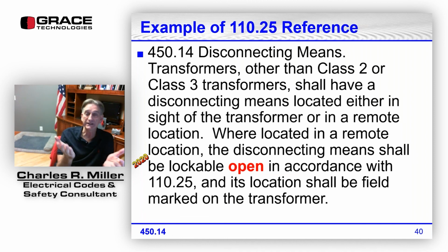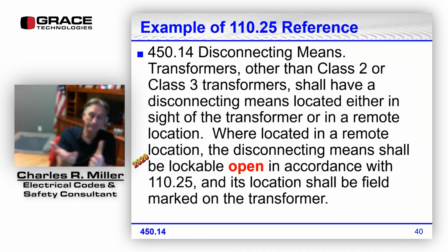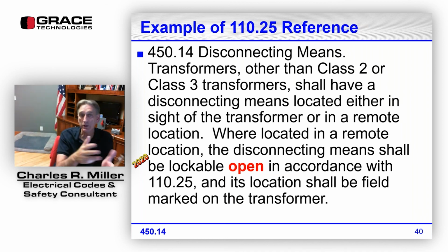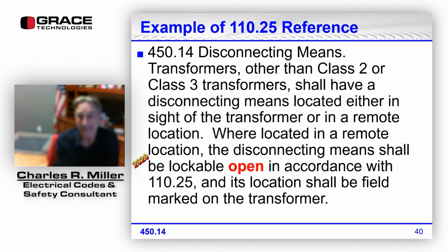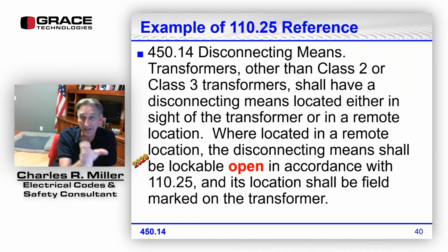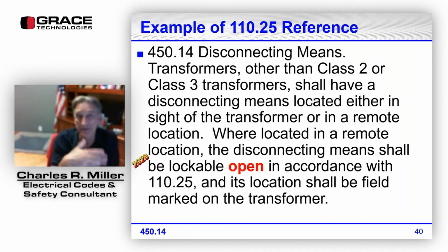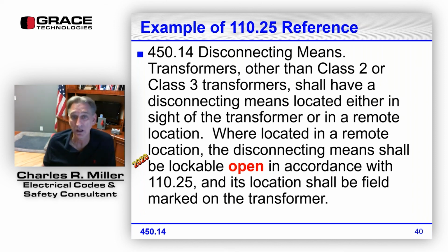So say we've got a disconnecting means at the transformer and we have a three-pole breaker at the panel board. We're wanting to shut off power to the disconnect itself in front of the transformer. Well, maybe we've got a three-pole breaker supplying power to there, so we can use an aftermarket device to put on that three-pole breaker, turn it off and lock it out and tag it out. That breaker is upstream from the safety switch at the transformer, so the locking device does not have to remain in place with or without the lock.